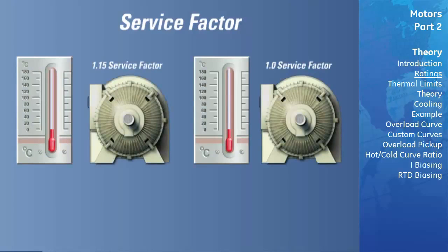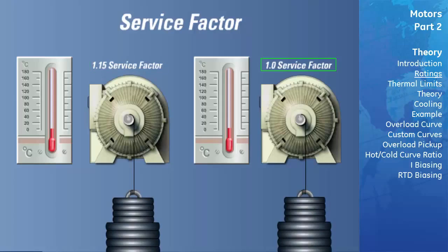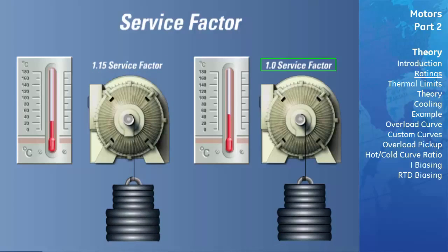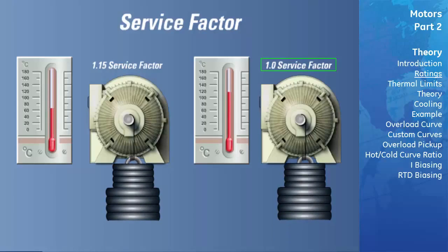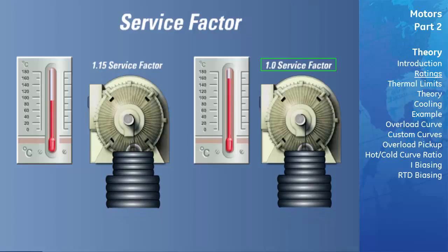Service Factor. For a given insulation, a motor with a 1.15 service factor has a lower temperature rise than a motor with a service factor of 1.0. This allows the motor to operate close to the service factor without exceeding rated temperature limits. When voltage and frequency are maintained at nameplate values, the motor may be overloaded up to the horsepower obtained by multiplying nameplate horsepower by the service factor. At a service factor load greater than 1.0, the motor's efficiency, power factor, and speed will differ from the nameplate, but the locked rotor current and breakdown torque will remain the same.